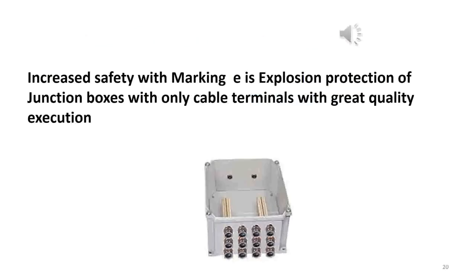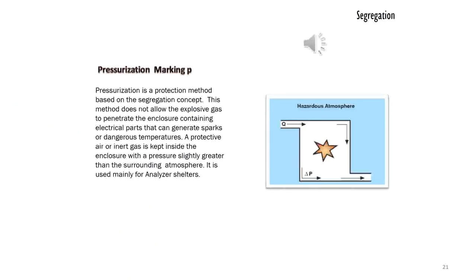Increased safety with marking E is explosion protection of junction boxes with only cable terminals with great quality execution. Pressurization marking P. Pressurization is a protective method based on the segregation concept. This method does not allow the explosive gas to penetrate the enclosure containing electrical parts that can generate sparks or dangerous temperatures. A protective air or inert gas is kept inside the enclosure with a pressure slightly greater than the surrounding atmosphere pressure. It is used mainly for analyzer shelters.